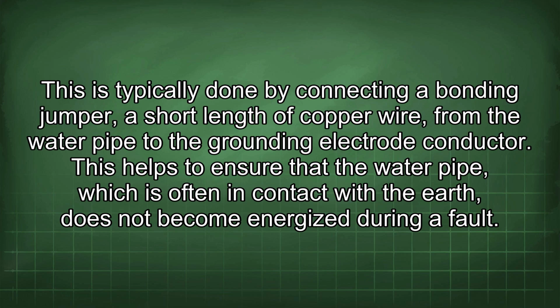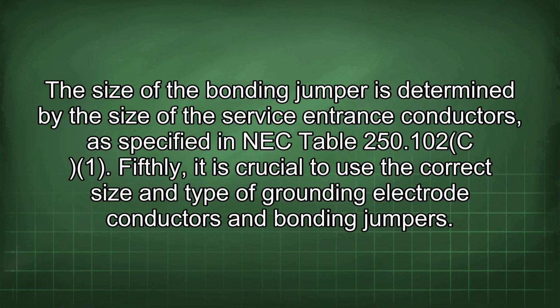This is typically done by connecting a bonding jumper, a short length of copper wire, from the water pipe to the grounding electrode conductor. This helps to ensure that the water pipe, which is often in contact with the earth, does not become energized during a fault. The size of the bonding jumper is determined by the size of the service entrance conductors, as specified in NEC Table 250.102(C).